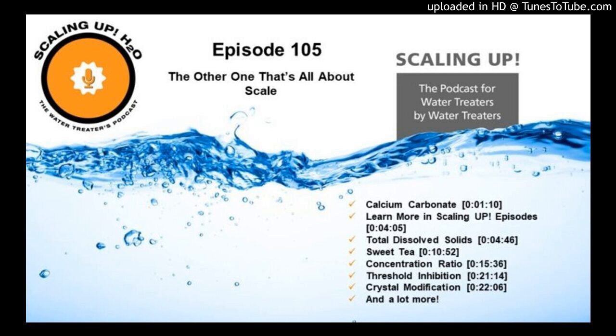So with that, let's say we're using a 200 gallon per minute makeup, and we're going to divide 1 into 6, so that equals 0.16. That's a coincidence, as it doesn't always work that way, so please do the math. And then I'm just going to multiply across. So I take my 200 gallons per minute makeup, multiplied by my 1/6, the reciprocal of my concentration ratio, and I find that out of that 200 gallons a minute, I am bleeding 32 gallons per minute.